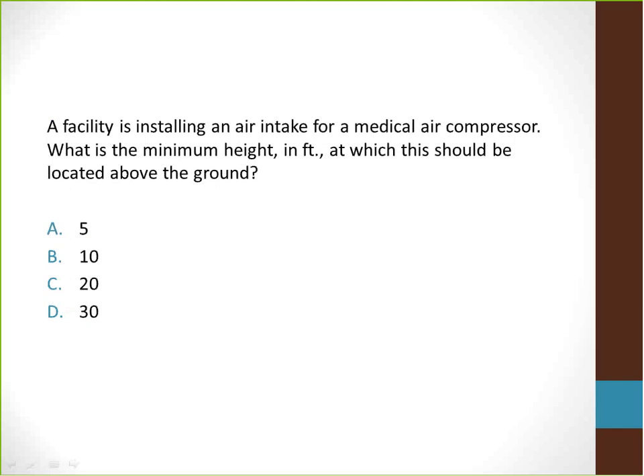A facility is installing an air intake for a medical air compressor. What is the minimum height in feet at which this should be located above the ground? Is it A, 5; B, 10; C, 20; D, 30? C is the correct answer here because 20 feet is the minimum distance required by NFPA 99.